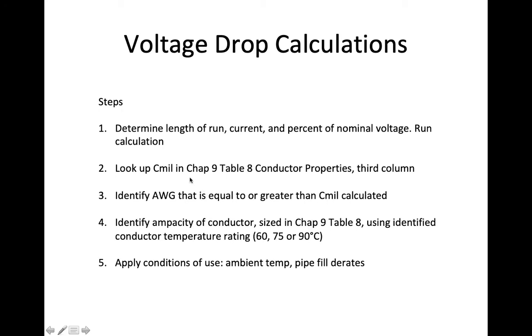Step 2. Look up the Cmil, or the answer from that equation. Chapter 9, Table 8, Conductor Properties, third column. So I'm going to go back to page 689, look at the third column, and match up a Cmil number with a gauge number.